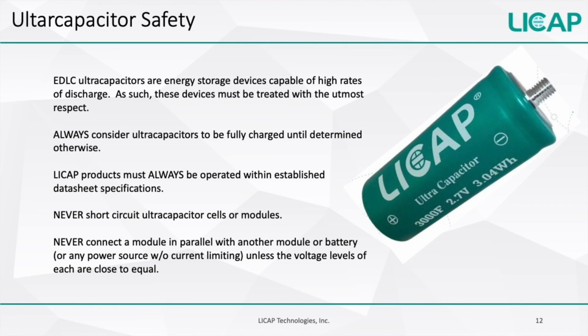Finally, last but not least, ultracapacitor safety, and this is very important. EDLC ultracapacitors are definitely an energy storage device with that low ESR we talked about, capable of very high rates of discharge. So you have to treat these devices with the utmost respect, especially if you've got a lot of them in series, talking in the hundreds of volt range. You should always consider an ultracapacitor to be fully charged until determined otherwise. I've seen people put something across an ultracapacitor, and you wouldn't believe the arcing that can happen.